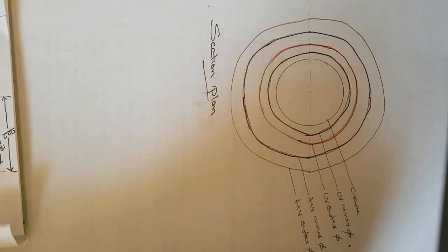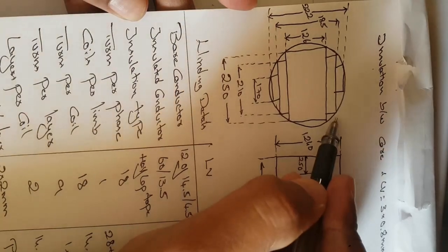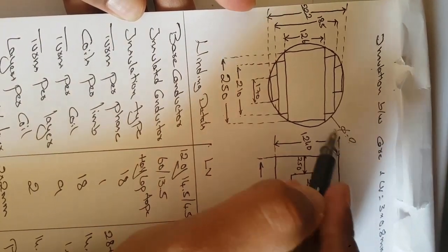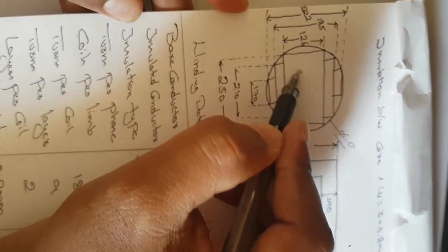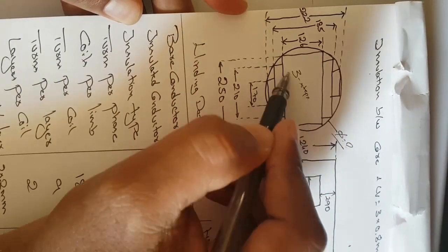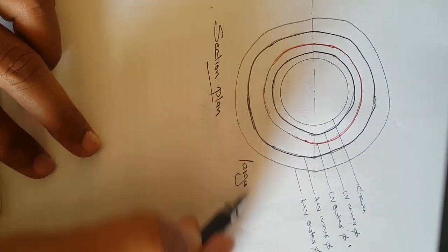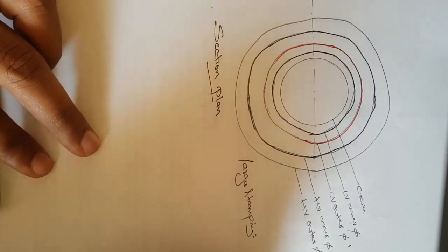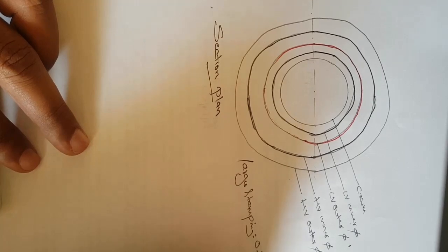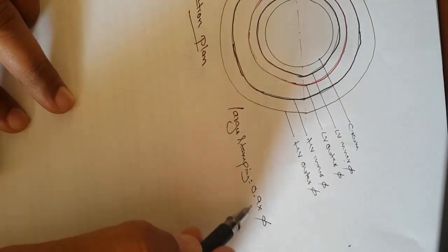And you can also see that here the step sizes are given, but the circumcircle dia is not given, so I need to calculate it. The given cross section is a 3-stepped. If it is a 3-step, as we know, the larger stamping size is equal to 0.9 times the circumcircle dia.